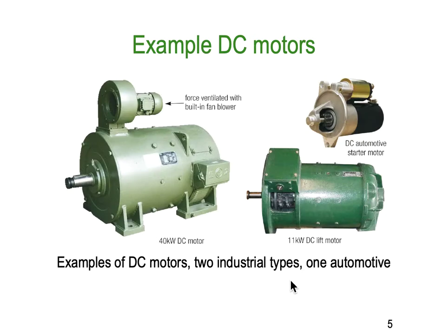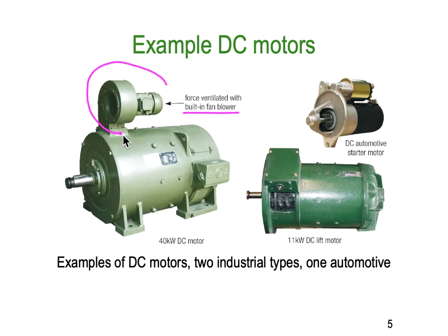Here are some examples of DC motors. The first is a large DC motor. DC motors are often used because of their very good speed control, especially at low RPMs — you can achieve full output torque. However, at very low speeds you don't get much ventilation from the motor's fan, so quite often they have a separate forced-ventilation fan built in. This one is a 40 kilowatt machine.